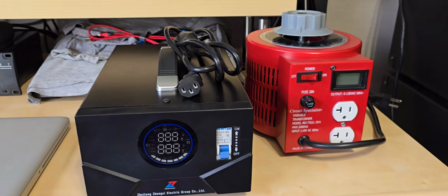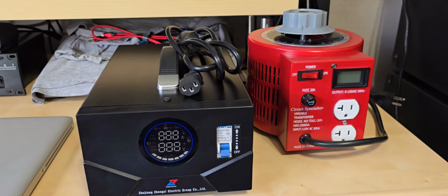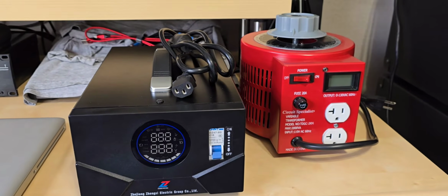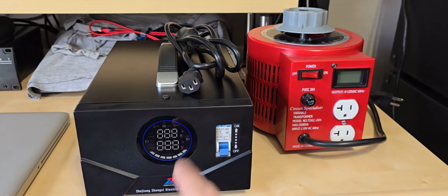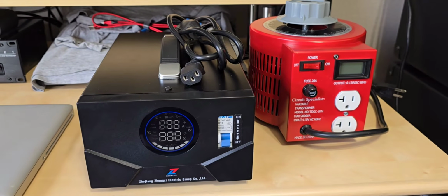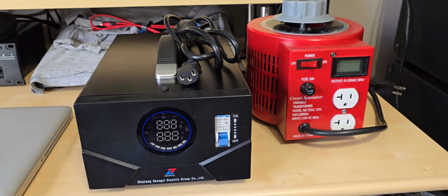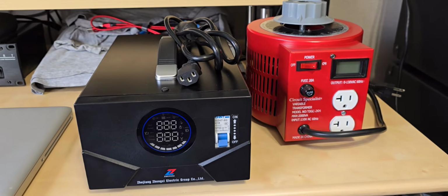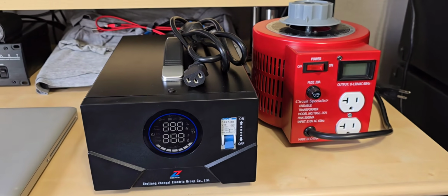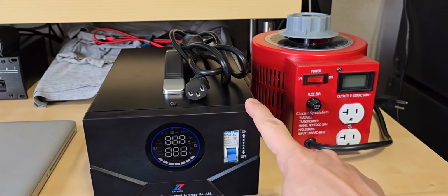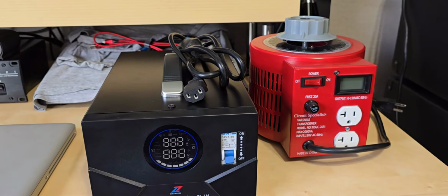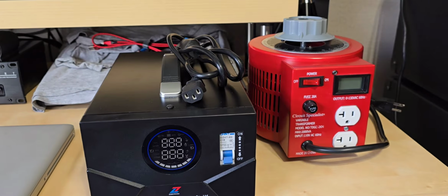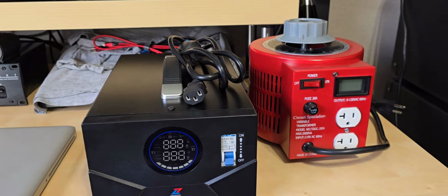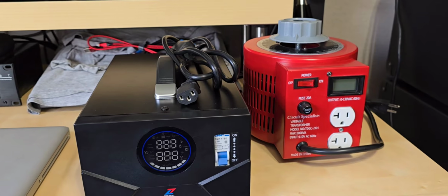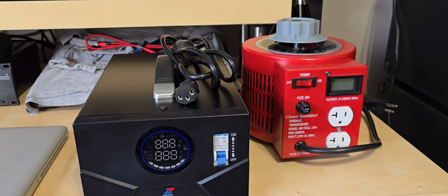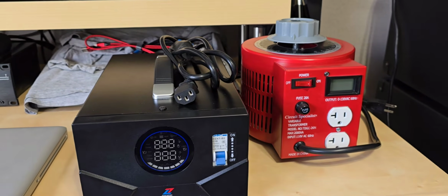Now, the last feature I wanted to touch upon that I wasn't able to go into in much depth in the first video was the thermal protection. This microcontroller is also monitoring the temperature of the transformer inside so that if it gets too hot, it will also shut itself down. I was able to find out from the manufacturer that it is a Class F, as in Frank, designed toroidal transformer, which means that if you look that up, 150 degrees Celsius is the maximum temperature for those coils to be operating before they start to see any kind of failure.